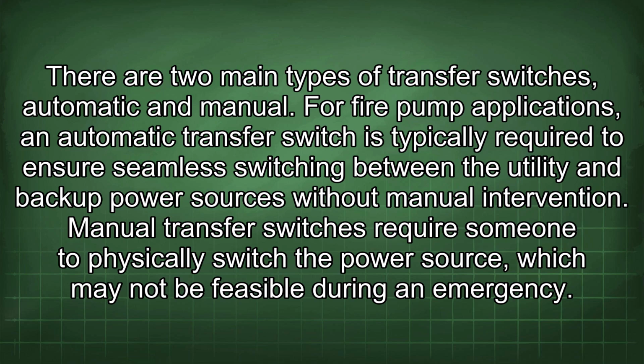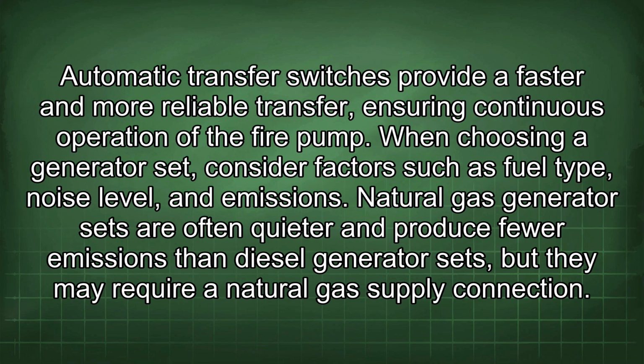For fire pump applications, an automatic transfer switch is typically required to ensure seamless switching between the utility and backup power sources without manual intervention. Manual transfer switches require someone to physically switch the power source, which may not be feasible during an emergency. Automatic transfer switches provide a faster, more reliable transfer, ensuring continuous operation of the fire pump.